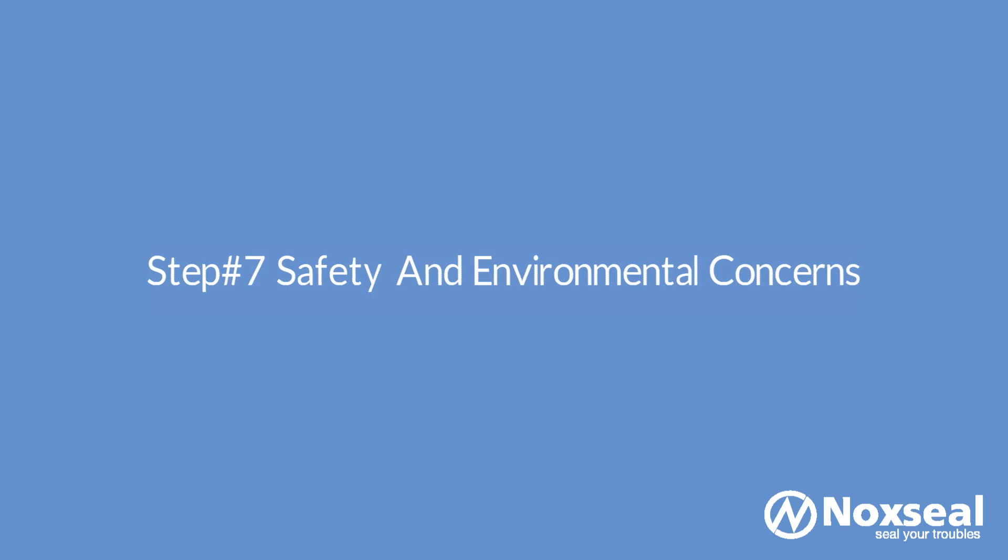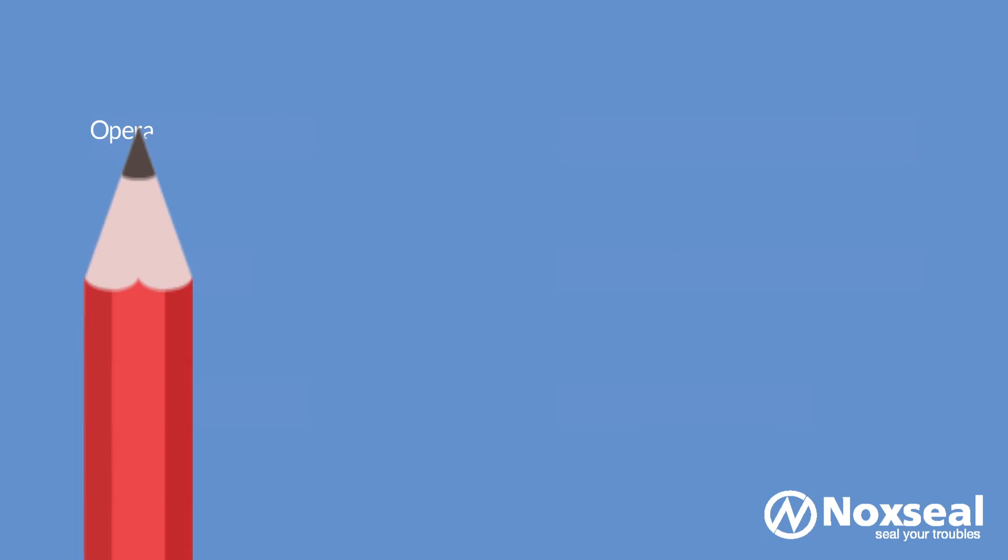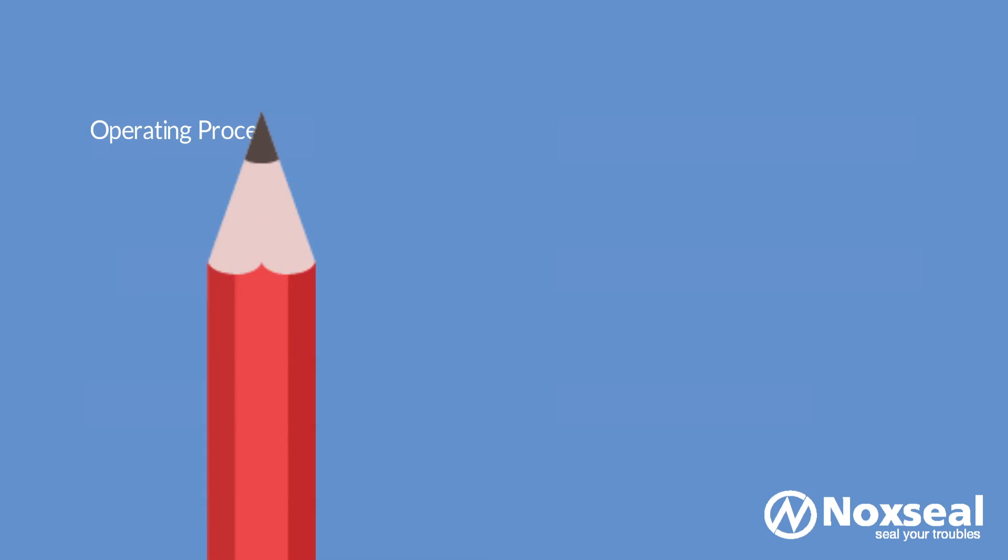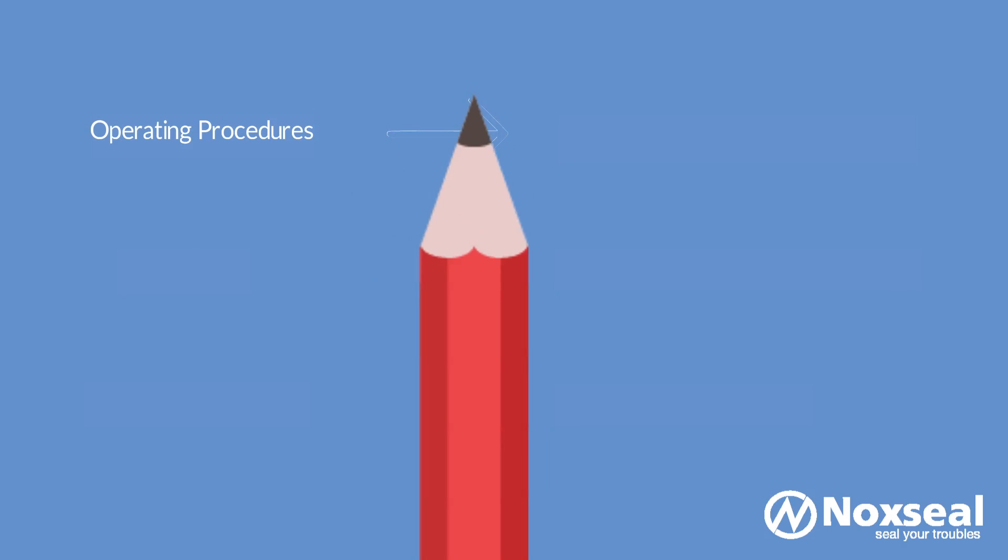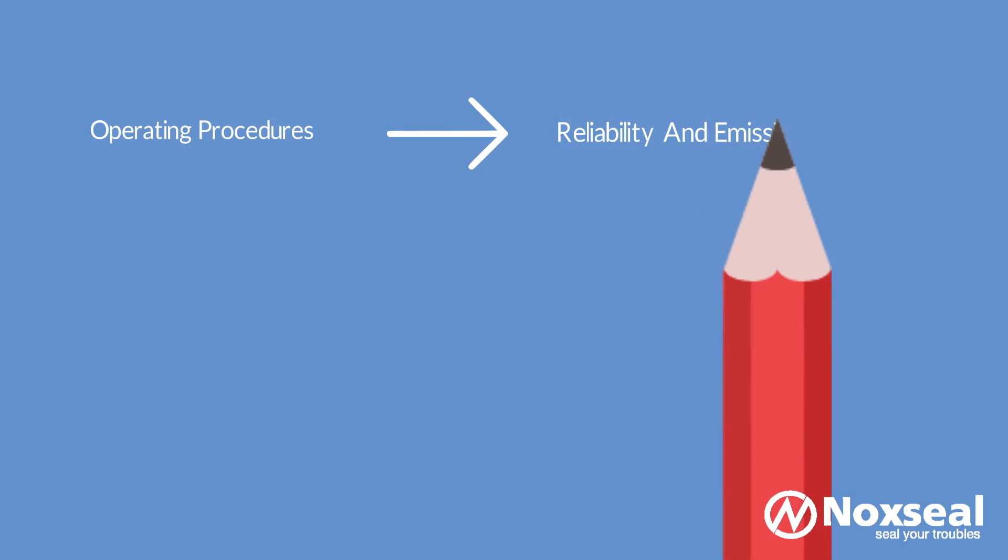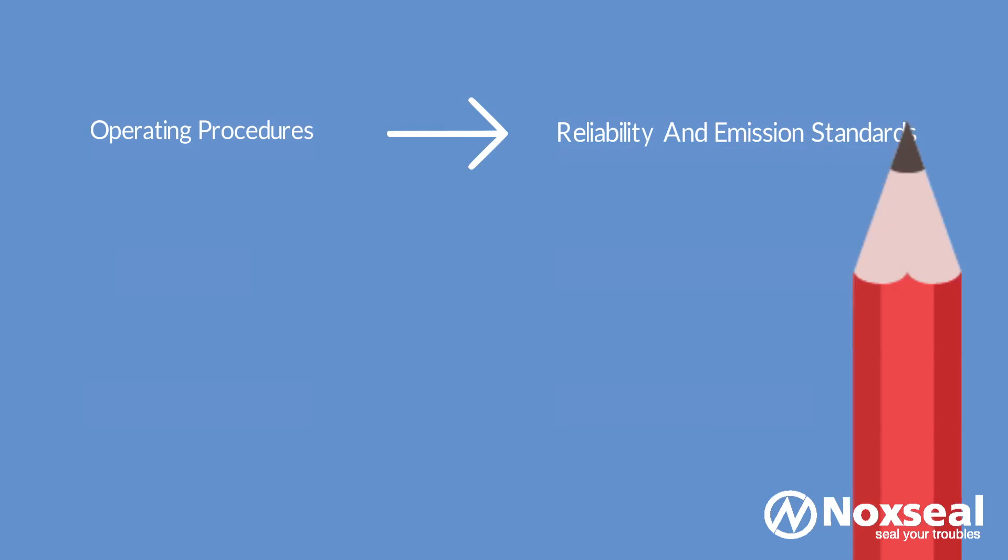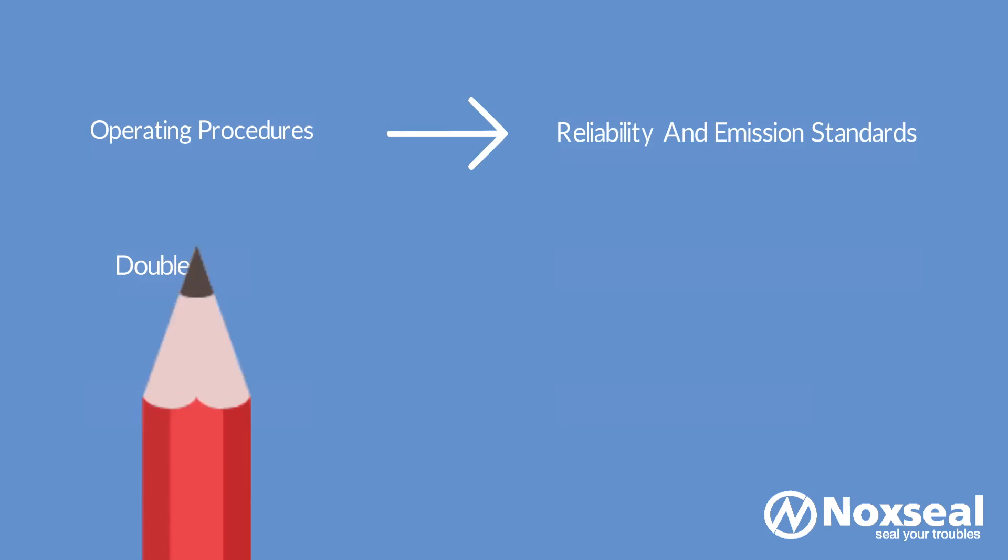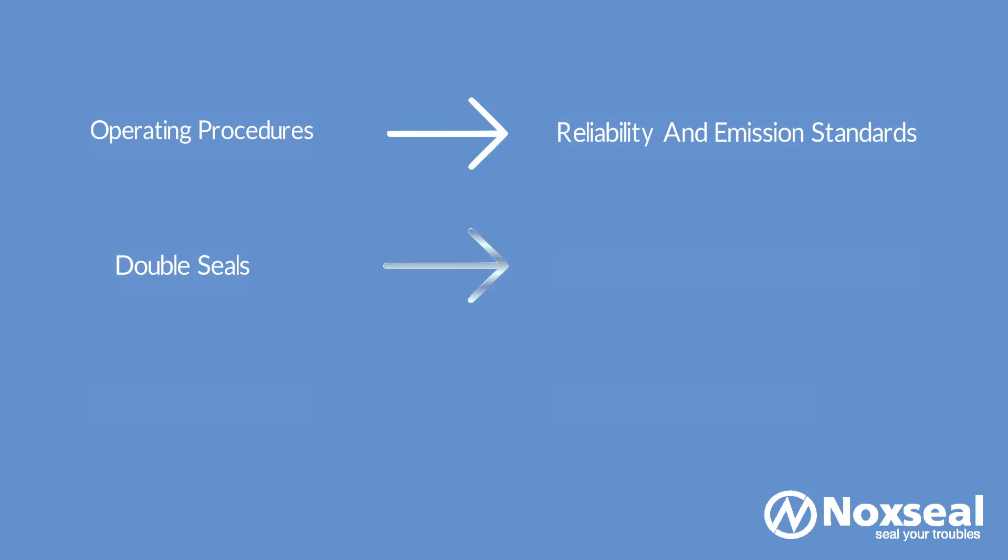Step 7: Safety and Environmental Concerns. Every plant has its own set of standards and operating procedures when it comes to mechanical seal reliability and emission requirements. The seal type and arrangement selected must meet the desired reliability and emission standards for the pump application. The safety of human beings handling the pump is of prime importance, so are the permissible emission standards. To be on the safer side it is better to use double seals that work as better sealants and are more reliable.